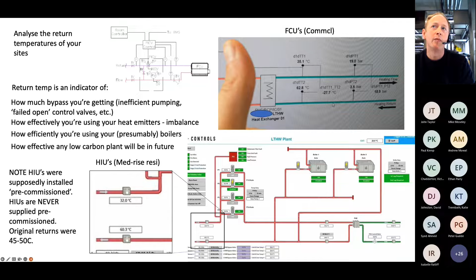Your top right, ignoring the fact that the flow and the return temperature probes are in the wrong place, which the eagle eyes among you may have spotted, you are still getting a fan coil system that's giving you about a 30-degree delta. That's good. That's not bad. You'd want better, but as soon as you start seeing things where, for instance, in the next slide, you start seeing the delta Ts coming incorrect, that gives you a bit of a clue on your BMS that something actually is fundamentally wrong.